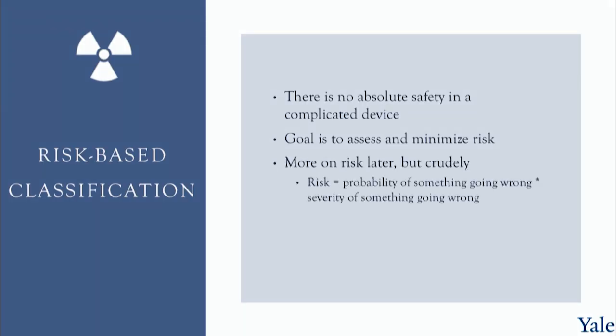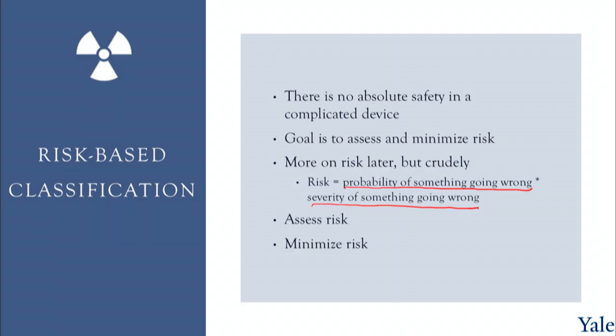We're going to look at risk-based classification. First, an acknowledgement that there's no such thing as absolute safety in any complicated device — the goal is to assess and minimize risk at all points. Risk is a combination of the probability of something going wrong and the severity of that outcome. If something is highly likely and the outcome is very bad, it's high risk. As those two factors decrease, we go to medium risk, low risk, and so on. The risk level defines which class a device falls into.